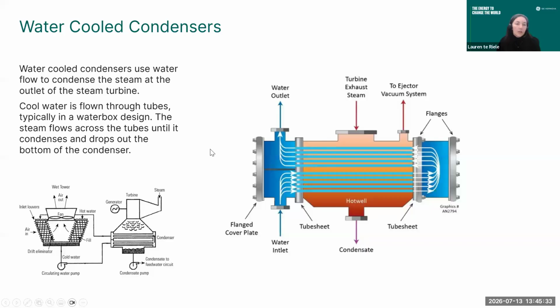Typically, as I note here, a lot of condenser designs are water boxes. They don't have to be, but what that means is you can see, even though there's individual tubes passing through here, they all have a shared header and a shared exit. So you have a large water volume at the front. All that water is pushed through the tubes, goes all the way around, so passing through the steam heat exchange area twice before it comes back out the outlet.